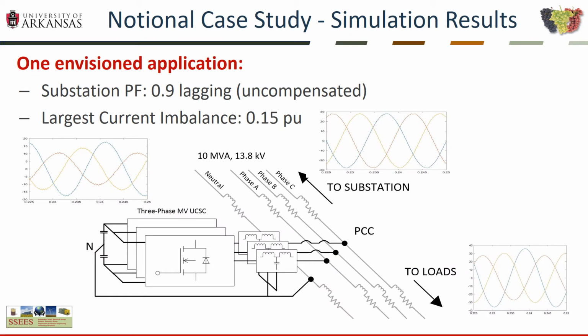This slide presents a potential application for the static compensator. We are assuming a substation having a power factor of 0.9 lagging, uncompensated, and the largest imbalance between two phases is 15%. The figure shows at the top the substation, at the bottom the loads, and towards the left the connection of the medium voltage unbalanced current static compensator. The loads are imbalanced. On the top left the static compensator injects currents to compensate the imbalanced loads, resulting in the substation currents being balanced.